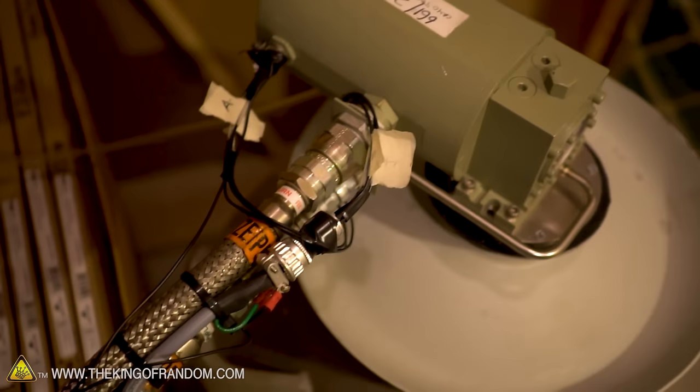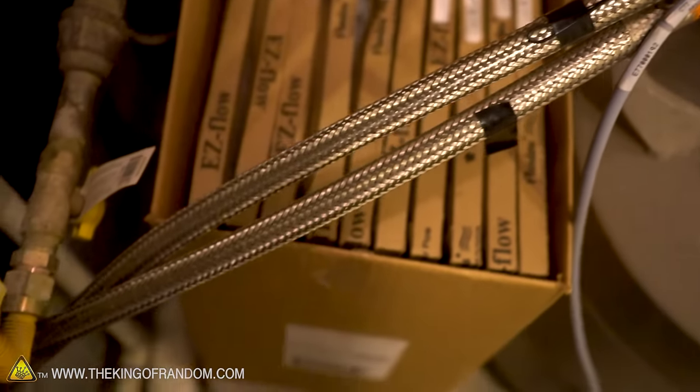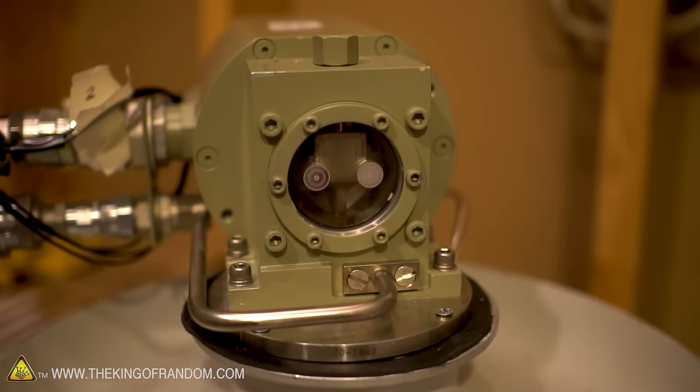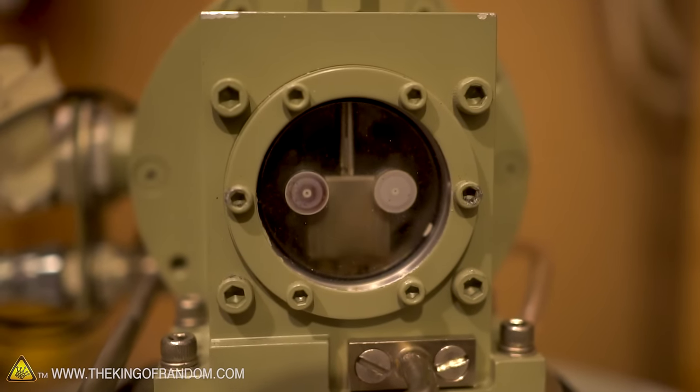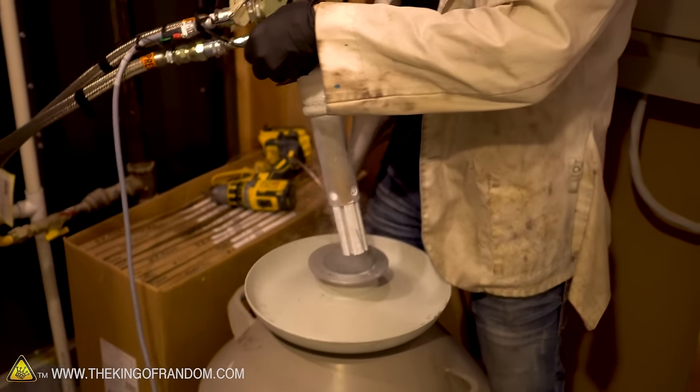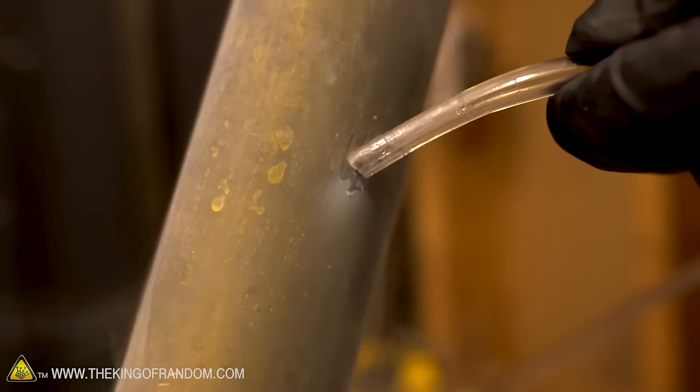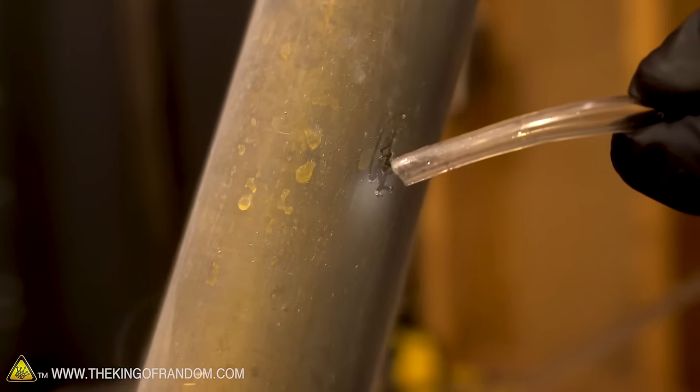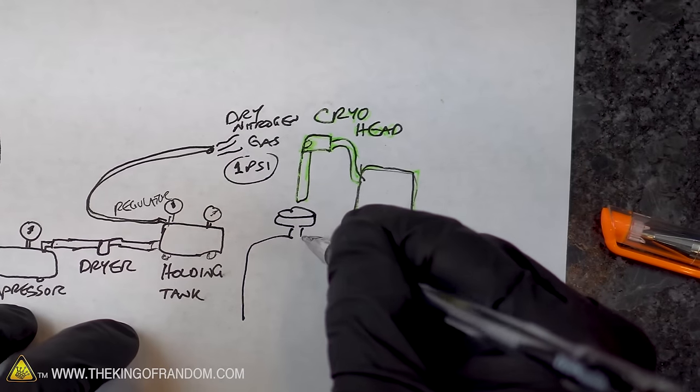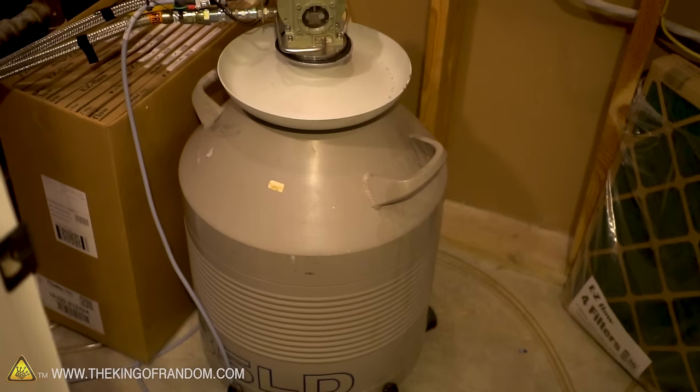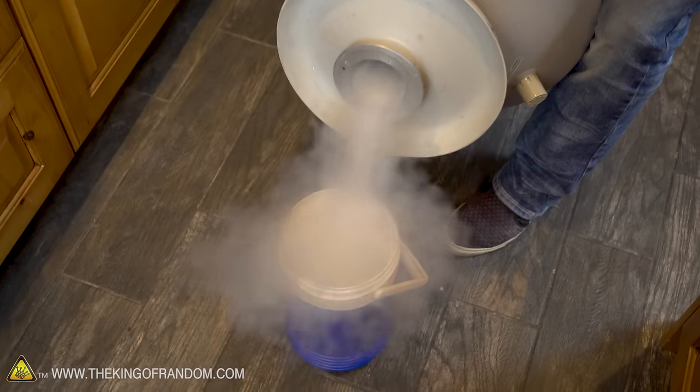So now that you've got the basic concept, let me explain in a little bit more detail how a helium compressor works. It's charged up with helium gas in a closed-loop system. The helium gas is compressed where it heats up tremendously, and we need some kind of system to cool it down, which I'll talk about in just a minute. But once it is cooled down, it can travel to the cryo head where it's rapidly expanded and cools down to a temperature lower than the boiling point of nitrogen. So what would happen if we had a surface that was colder than the boiling point of liquid nitrogen and we had a small vapor of nitrogen gas blowing at it? That's right, it's going to condense and form small droplets and drip down to the ground. Now if we're able to catch those droplets into some kind of glorified thermos, a dewar if you will, then theoretically over time those droplets would add up and produce bucketfuls of liquid nitrogen. And that's it guys, that is exactly how we make liquid nitrogen.